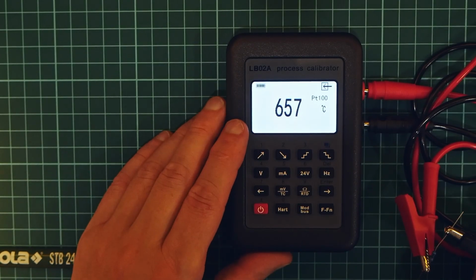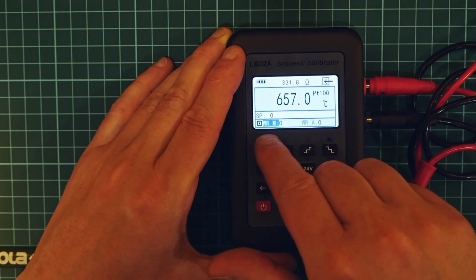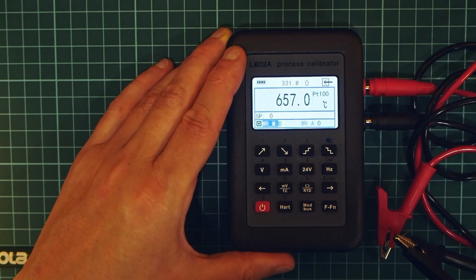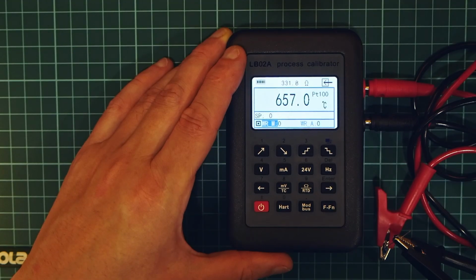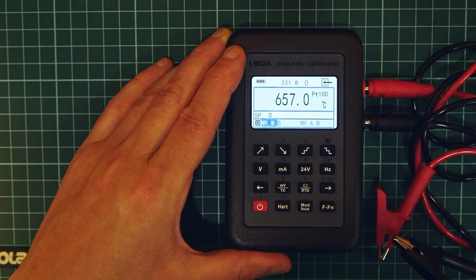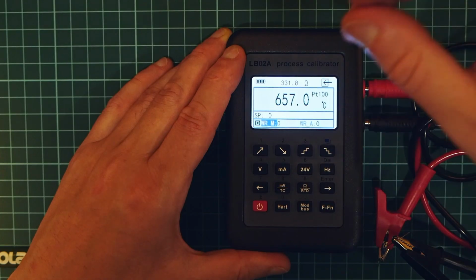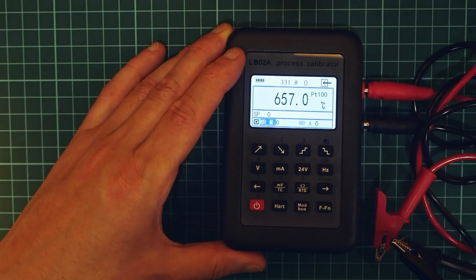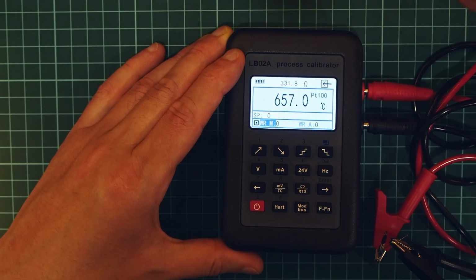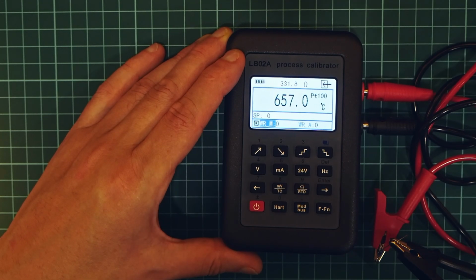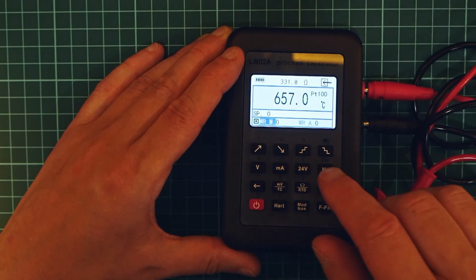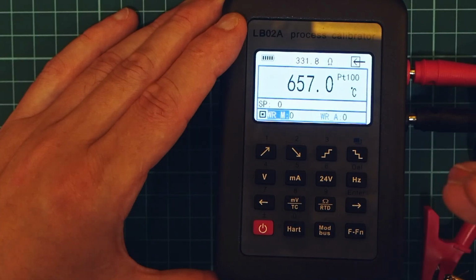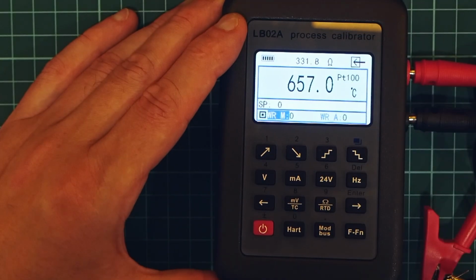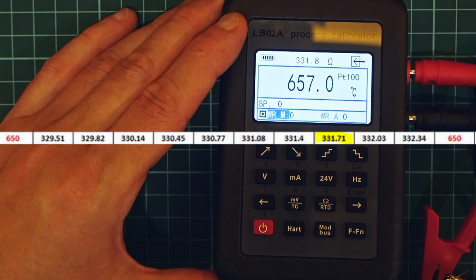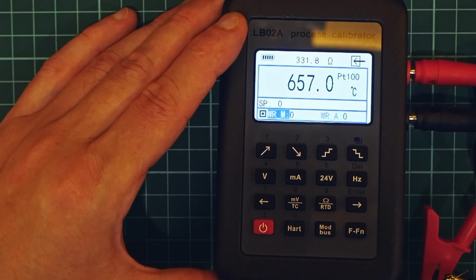And one more thing regarding this PT100, if we go to function, we have this wire compensation for wire resistance. Let's say our RTD is connected to the device, and then it goes through wire, let's say 20 meters of wire. So we disconnect this wire from the RTD, short it out, measure the resistance of the cable itself, and then you have this. It usually should be, well, a few ohms. If the cable is good, not damaged, it should not be a lot of ohms. So we can go to function mode and enter this resistance, and it will be subtracted when measuring temperature. When a 3-wire RTD is connected to an analog input card, this is exactly what the third wire is doing, measuring wire resistance.